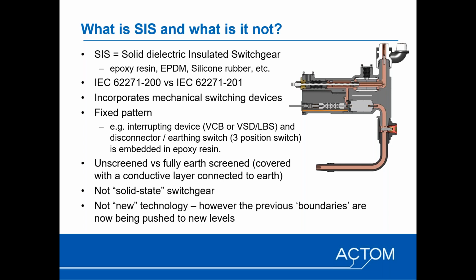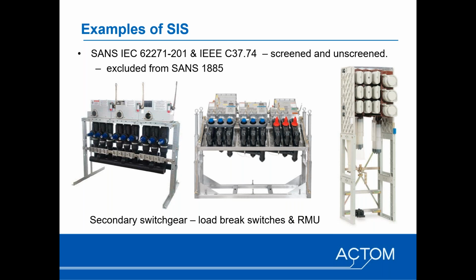However, what we've seen in the industry is there's been some drivers, for example, the drive to move away from SF6 and other fluorinated gases to more environmentally friendly insulating mediums. So that's been a driver, but also developments in the solid dielectric technology has really started to push the boundaries in terms of the ratings that can be achieved, both in terms of voltage as well as current. Today, most solid dielectric switchgear has been limited to secondary switchgear, typically rated up to maybe 630 amps and 12 kV.